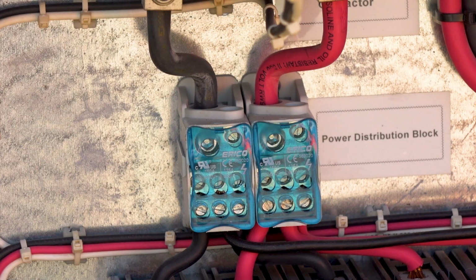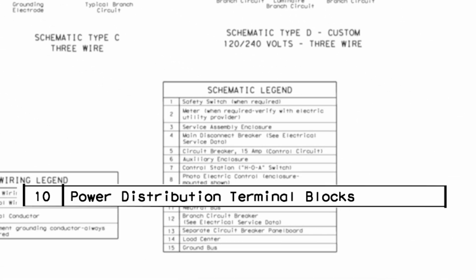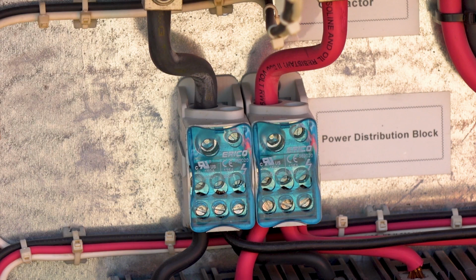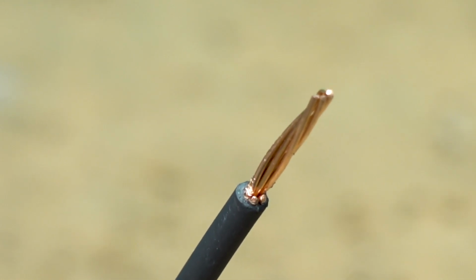Power distribution blocks distribute power from the load side of the lighting contactor to the branch circuit breakers in the service. The distribution blocks are noted on the line drawing and should be marked within the panel. Inspection of the blocks is limited to confirming their installation is secure and done in a neat and workmanlike manner. All strands of the conductors connected to the blocks should be intact and free from nicks and cuts.